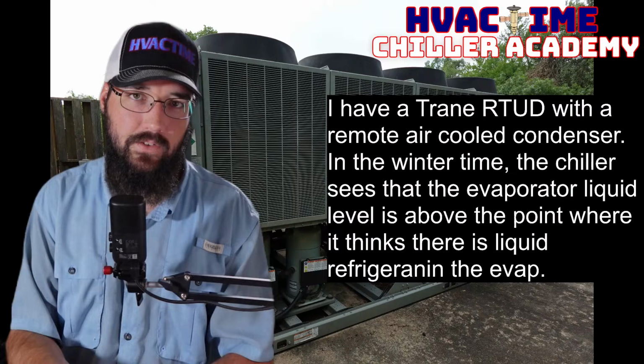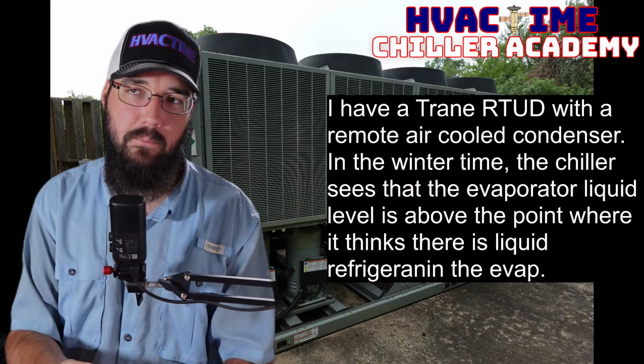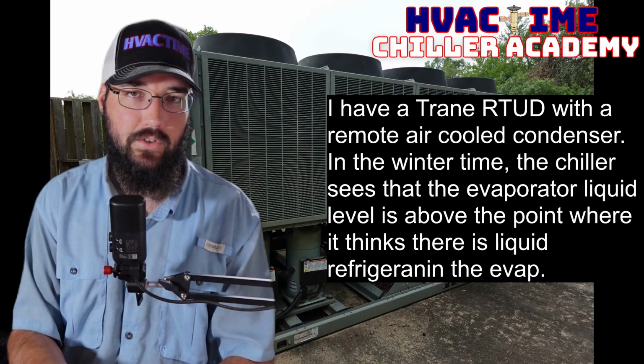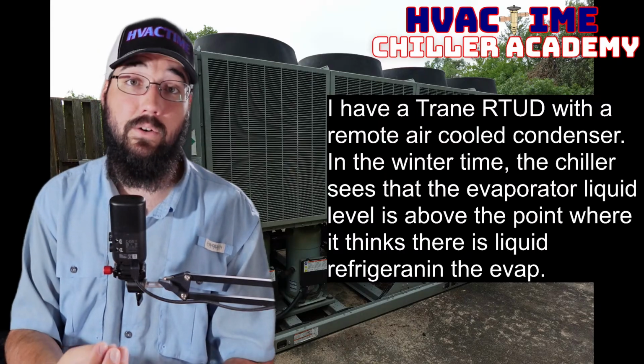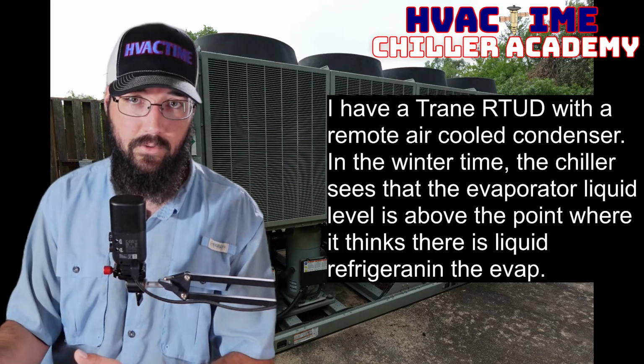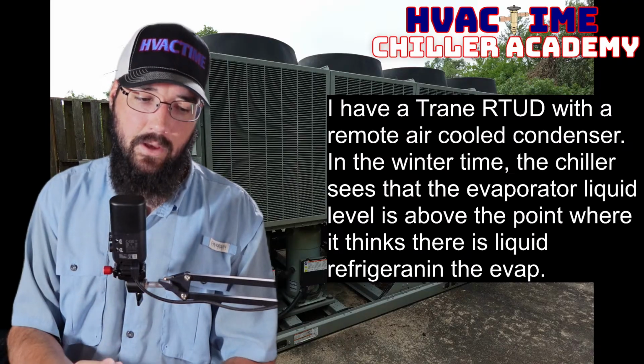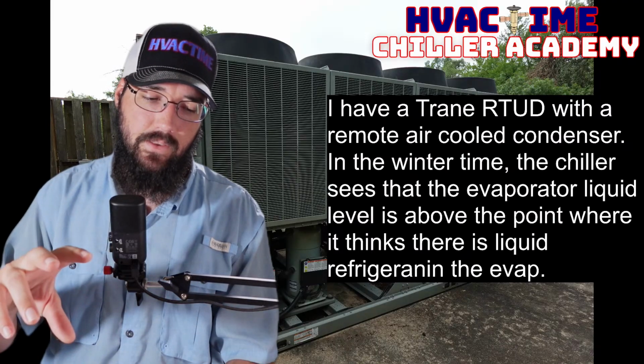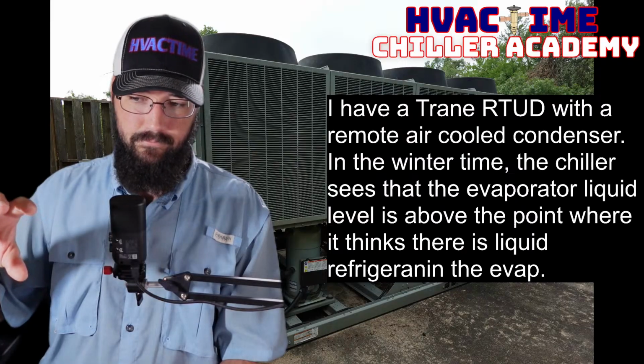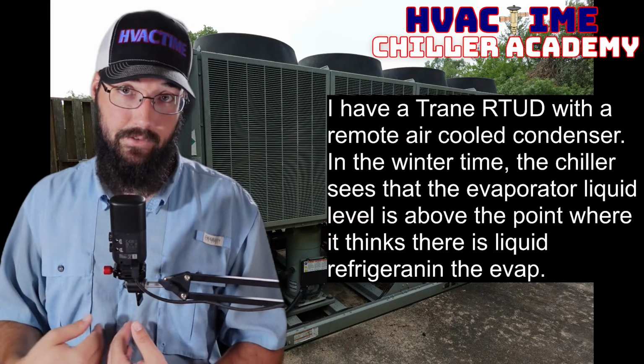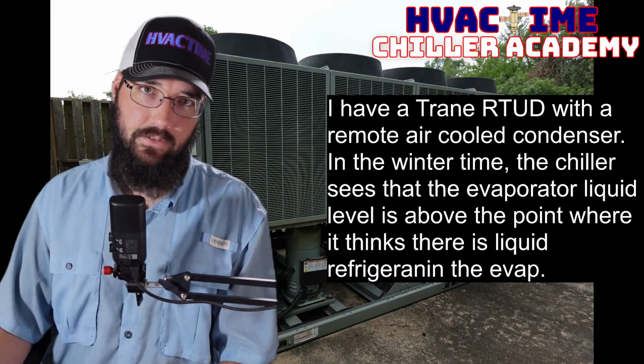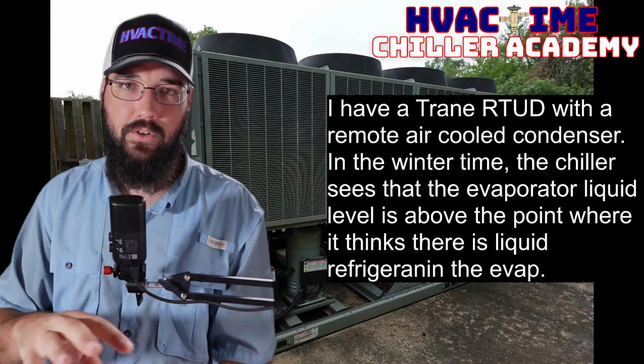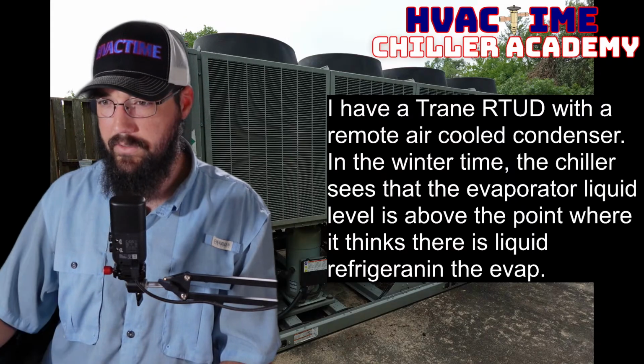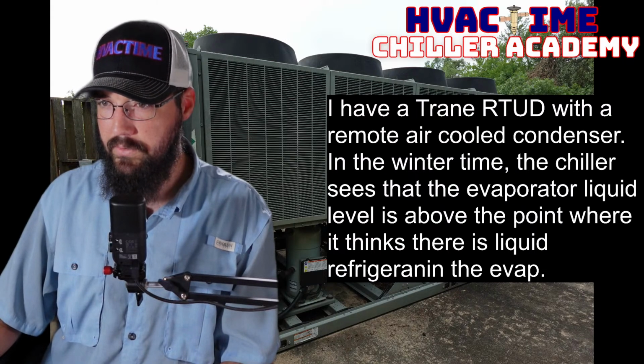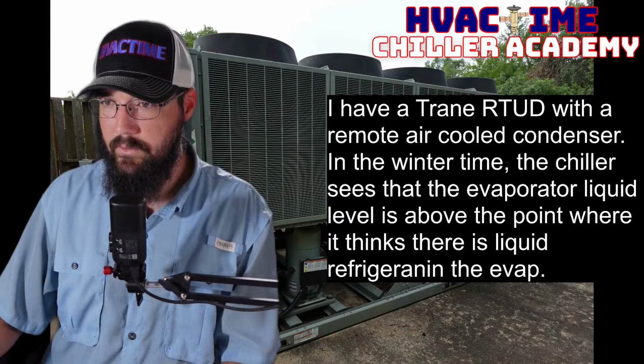So even if the sensor is not getting a false reading from the oil, let's just say that sensor had a good reading and it was actually reading refrigerant. Let's go that path. Then that would mean that it is because of the oil, I would say, because of that oil stacking in there. And being that you're seeing this on both sides, I think you said it's happening on both circuits. It's happening, both circuits. So the chiller is pumping down because of low ambient.